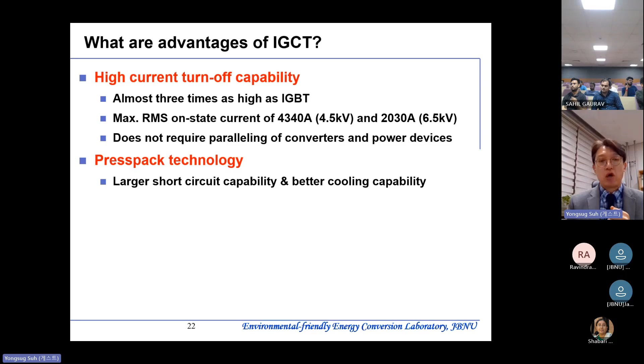IGCT also comes as a press-pack technology. IGBTs these days use soldering from the outside. Solder is the weakest link for the whole module technology, so under thermal cycling issues, IGBT might go into failure mode. But press-pack technology doesn't have these soldering or wire bonding issues, so it can sustain larger short circuit capability, better cooling, more reliable protection, and a simpler cooling system.